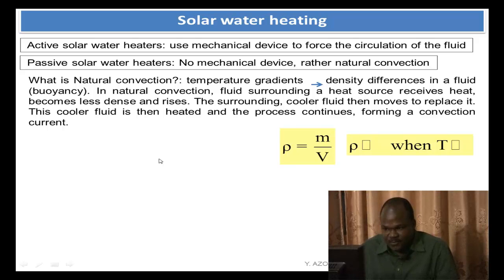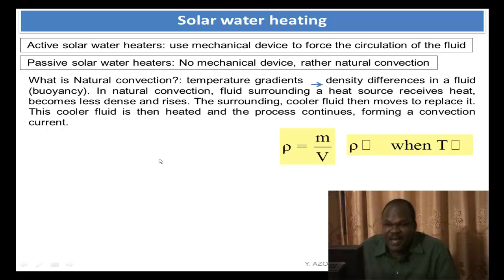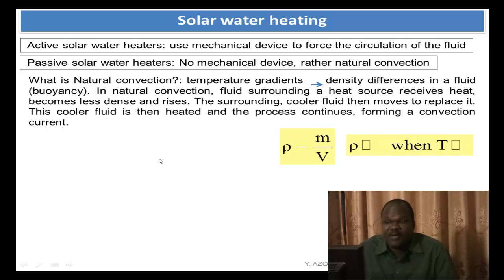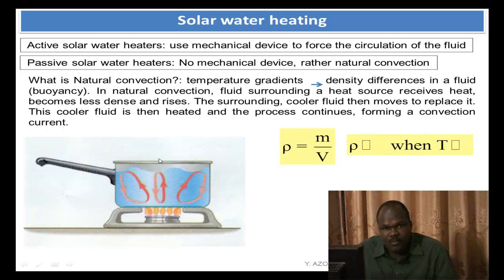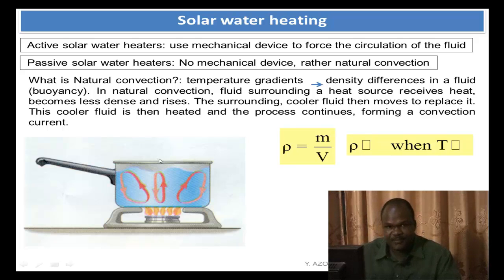Solar water heating. Basically, you have two types of solar water heating. You have the active solar water heaters that use a mechanical device to force the circulation of the fluid. And you have the passive solar water heaters — there is no mechanical device, it's just natural convection. Natural convection is caused by difference in density, and the difference in density is caused by a temperature gradient. Let's look at the example here.